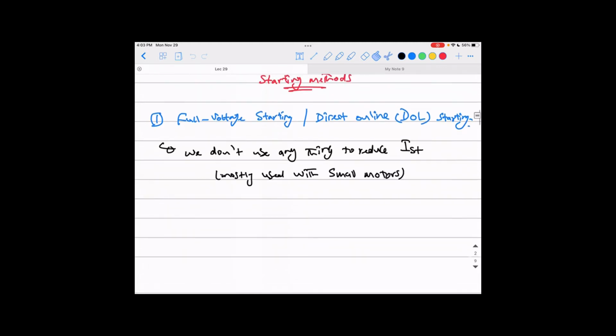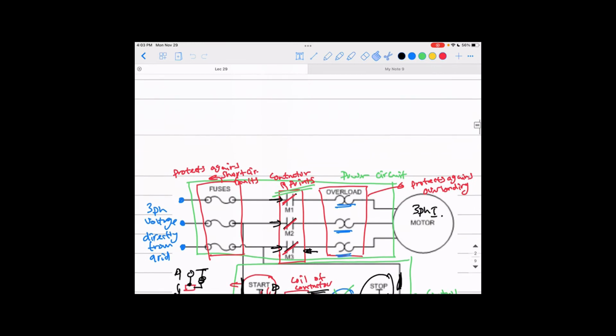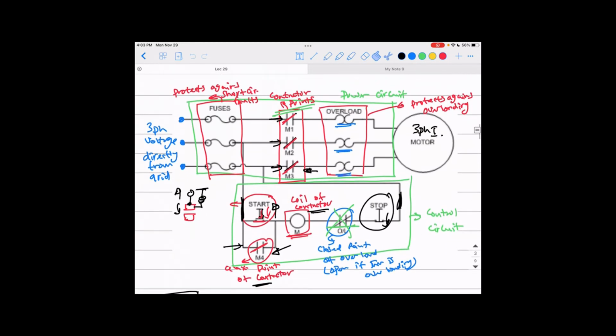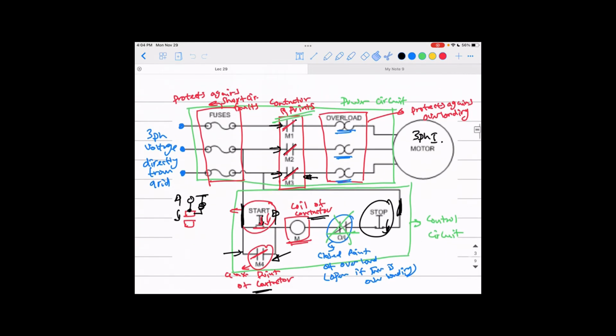That is, we don't use actually any method to reduce the starting current, just leave it alone. And this is used with small motors because whatever the current goes up, it's not that much. So we don't need to have a specific method to reduce a current that is already not that high. And that, like we said last time, is the control and the power circuits of the motor, which in the power circuit is basically a contactor, which is the three-phase switch that can be remotely controlled to just close or open.